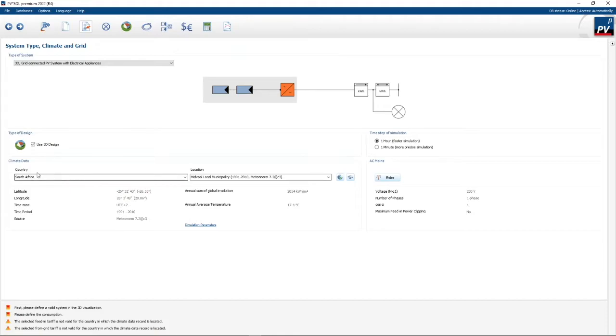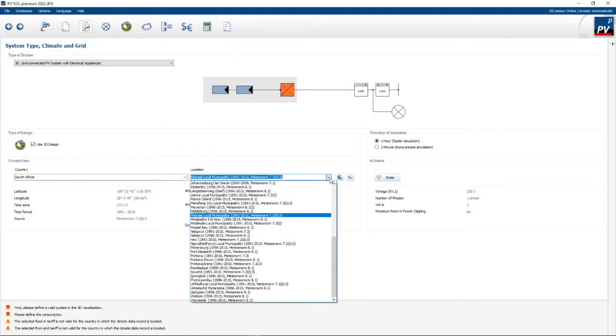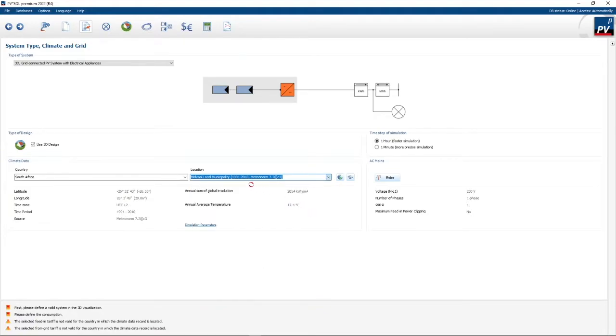The bottom left is where you set up your climate data. This is very important as PV Sol will use the climate data to simulate the PV system. Here we've selected South Africa and our location where the PV system is going to be. If the location is not already in the dropdown box, you can add it by clicking on the little globe to the right and selecting from a map. To the right, you set up the AC mains — in this case it's a single-phase 230-volt system.